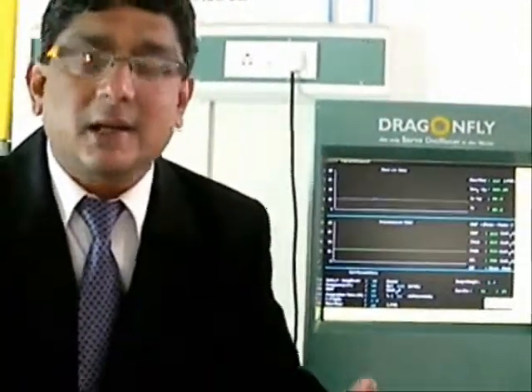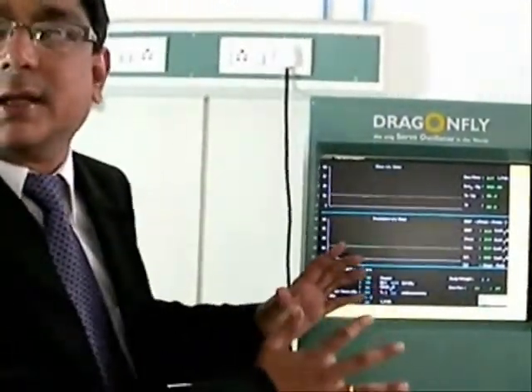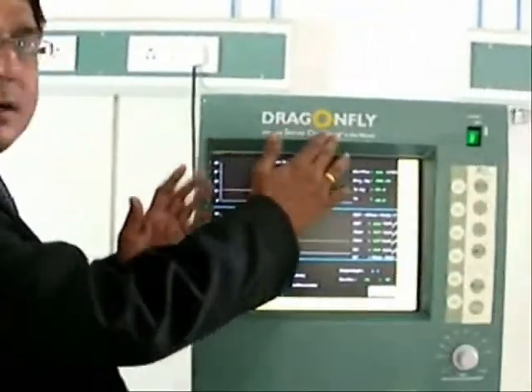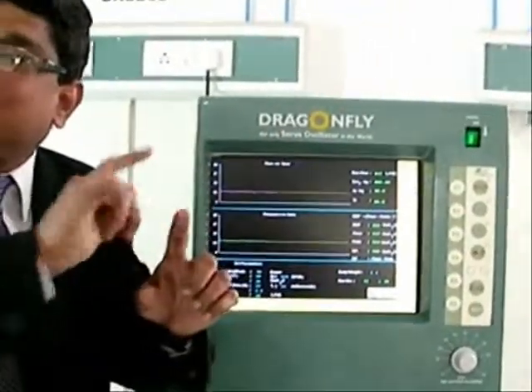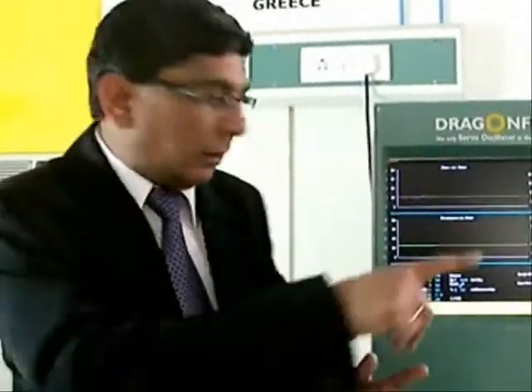So the basic logic is that we have given more stress to the clinicians, and we feel that the clinician should attend the patient and not the machine. So that's why it's a servo control mechanism. You adjust or change any parameters like the amplitude, the inspiration time, the frequency, and your set mean airway pressure remains the same, and that is the servo control mechanism. So that's the beauty of this machine.